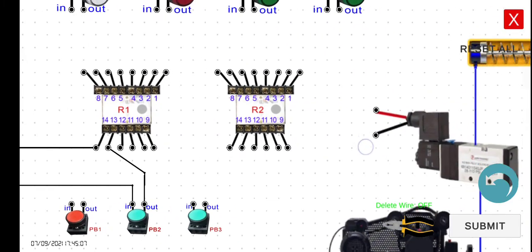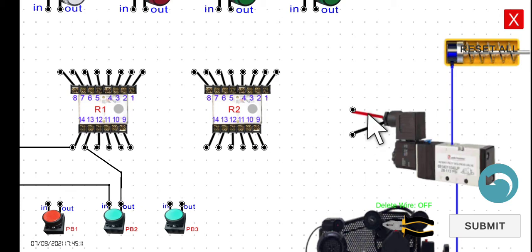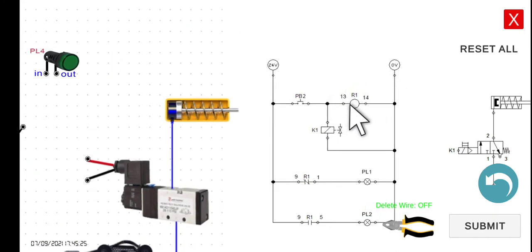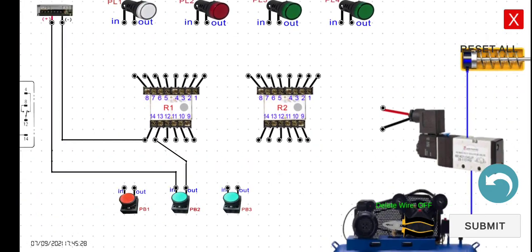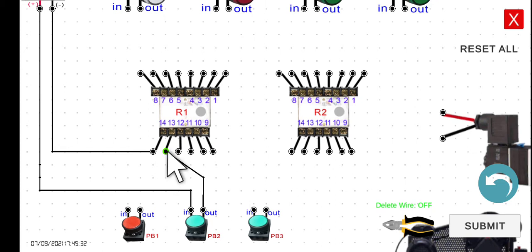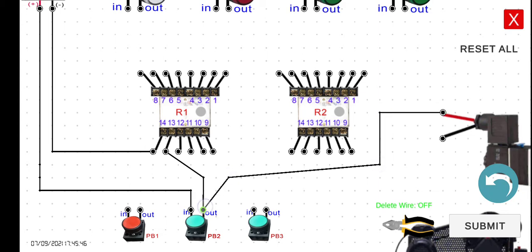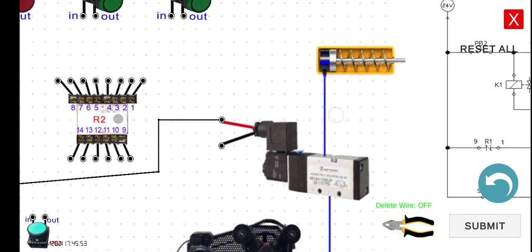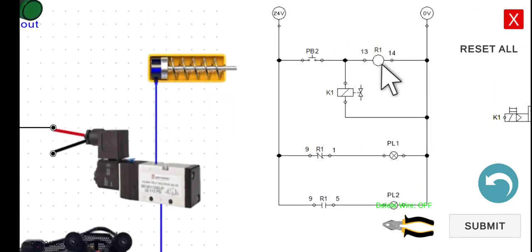At the same time, for K1 — take note of the polarity since we have the positive and the negative of our solenoid. This should be connected on the positive side of the circuit. We have to connect this one in parallel, so connect it to pin 13 of our relay — or we can also connect it to the output of PB2 since there is a wire connecting those two points. The negative of the solenoid we have to connect to pin 14 of R1 or to 0 volts.